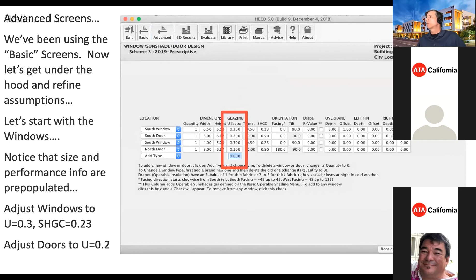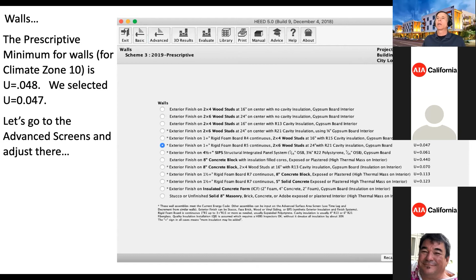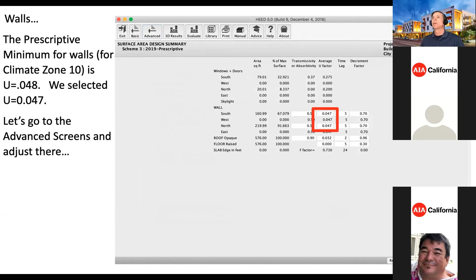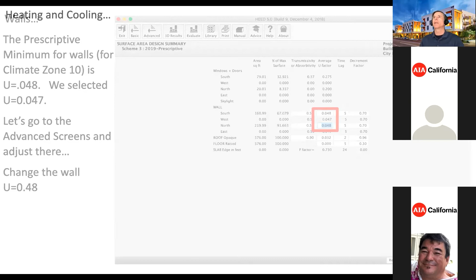On to walls. The prescriptive minimum for our climate zone was 0.048; we selected 0.047. If I were doing this anywhere but on this webinar, I'd leave the 0.047 alone — a thousandth of a BTU per square foot isn't going to make a real difference — but I want to get it right, to be exact. So I go to the advanced screens, find the wall information under surface area, and there it is: average U factor for the walls is 0.047. I'm changing that to 0.048 to be precise, and I'm done. Heating and cooling.